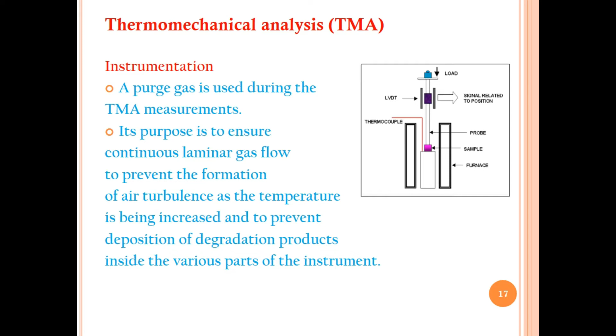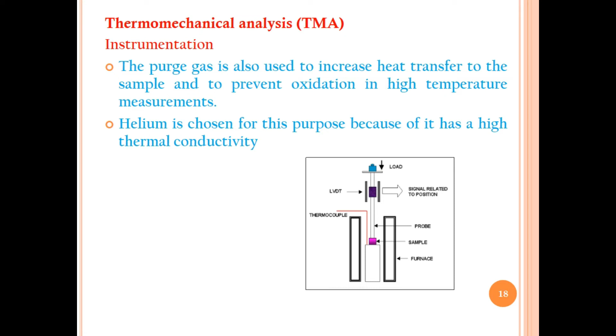Its purpose is to ensure continuous laminar gas flow to prevent the formation of air turbulence as the temperature is being increased, and to prevent deposition of degradation products inside the various parts of the instrument. Instrumentation continues. The purge gas is also used to increase heat transfer to the sample and to prevent oxidation in high temperature measurement, which has already been discussed. Helium is chosen for this purpose because it has high thermal conductivity. So the choice of gas also depends upon its thermal conductivity, and usually helium is chosen because of its high thermal conductivity.